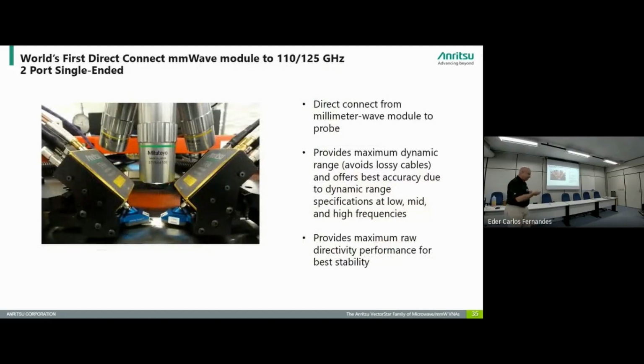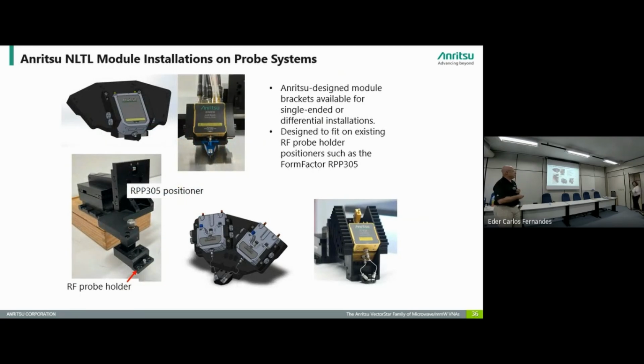The idea is to get better raw directivity because that's what gives you the best stability over time and temperature, because you don't want to have to calibrate all day long. You want to make measurements, not spend all your time calibrating. But that's how it used to be in the past, is that calibrations would drift because of this reason. So we've addressed a lot of those challenges over the years at high frequencies.